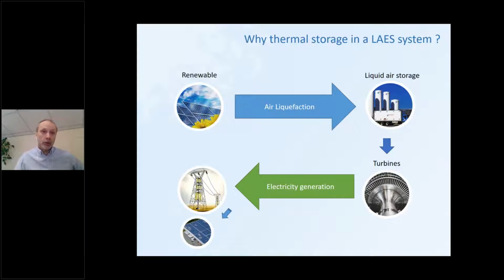Inversely, during electricity generation, the liquid air is expanded, which liberates a lot of cold energy at very low temperature - so this process produces cold energy. The generation process can also use heat to increase turbine efficiency. So the liquefaction and generation processes can be very complementary, but it's only possible to take advantage of this complementarity by using thermal energy storage devices, because liquefaction and generation never occur at the same time - so it's necessary to temporarily store the heat and cold energy.